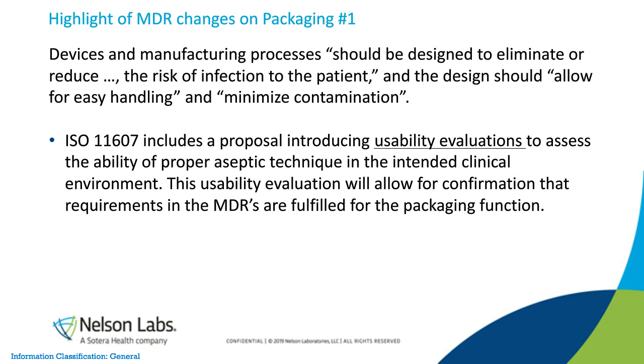With the introduction of usability evaluations, ISO 11607 wants you to assess the ability of aseptic techniques in the intended clinical environment. How is that package opened, and is it opened as its intended use? The usability evaluation will meet the requirement for the packaging function of the MDRs. You do that using a documented evaluation demonstrating the contents can be removed aseptically.